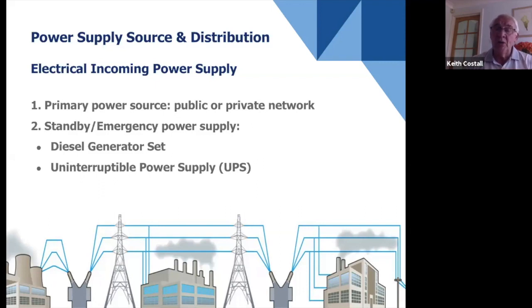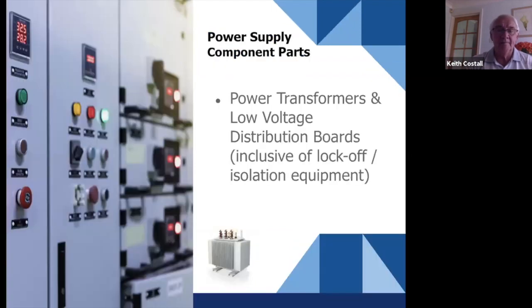The traditional way was to have a diesel genset. When we went from category 1 to category 2 or 3, we ran the AGL from the diesel genset, using the ring main as backup, since we could change over within that time frame. But the modern way is to have a UPS. So for standby power we have the diesel genset and a UPS. We started off with rotary UPSs, and now we're into the world of static UPSs—that's what we have today.